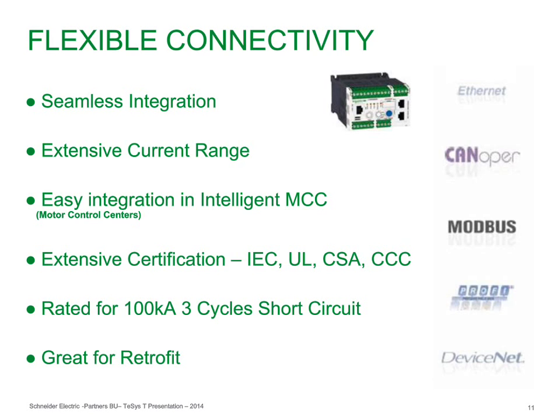Again, the current ranges with this are 100 amps and under, native to the unit, but we have software where we can run the secondary of current transformers through the TeSys T and have CTs up to 1,000 amps, which is over 700 horsepower at 480 volts, which typically is where medium voltage would be used. Also, if you have export requirements or other country requirements, this device not only is UL listed, it has an IEC listing, a CSA listing for Canada, and a CCC listing for China. So most places that you may export products or have products come in, we can meet with this. As well, in the U.S., we would like to know on a 3-cycle short circuit fault what the interrupt rating of this device would be. And so it's a full 100 kA interrupt rating on this device at 600 volts.